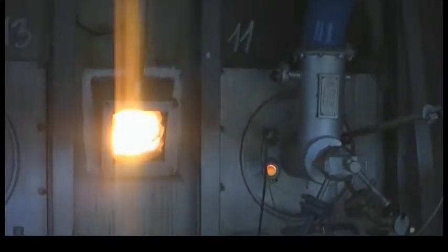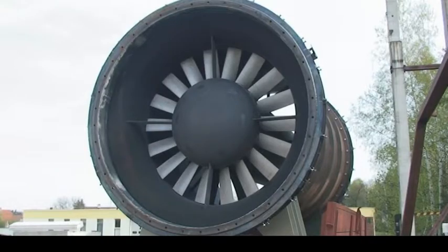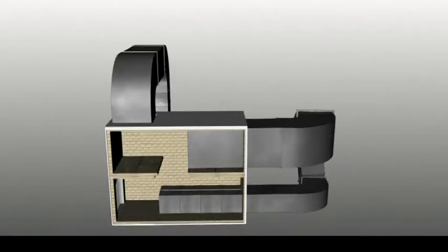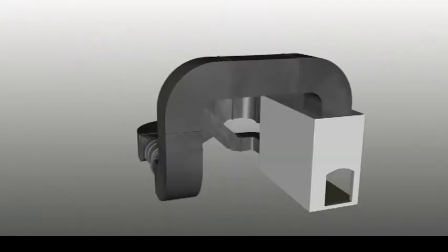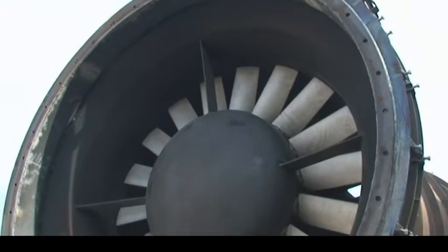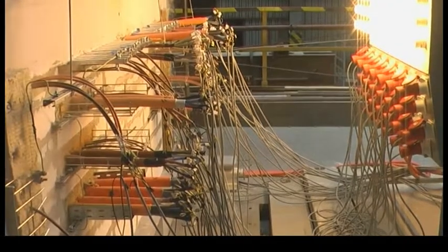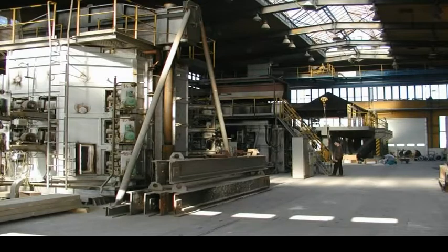The maximum furnace output, 5 megawatts, may be used in tests of extremely large products, for example smoke and heat exhaust ventilators. The diameter of the impeller of the biggest ventilator tested to date has been 3,000 millimeters. In that furnace, also cables and supporting cable constructions are tested to determine their functionality class in the case of fire. In the column furnace, the tested elements may be loaded up to 5,000 kN, and thus the real behavior of loaded elements in fire may be simulated, irrespective of element's type, column or load-bearing wall.